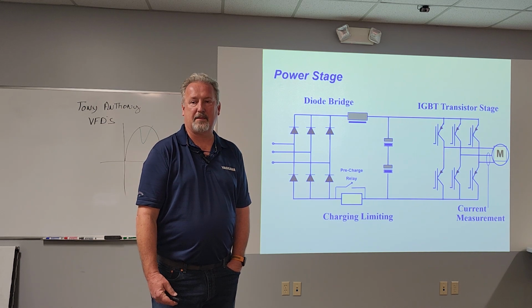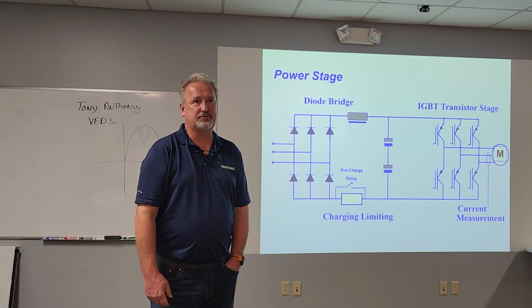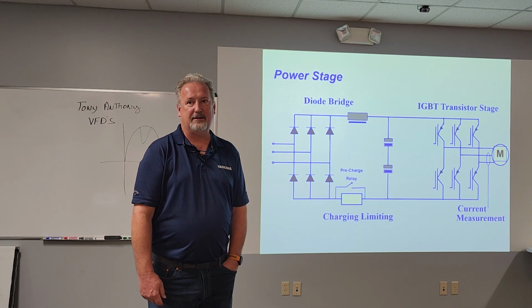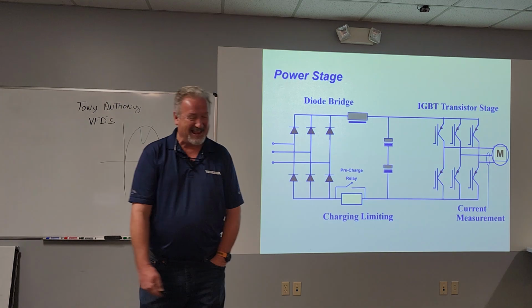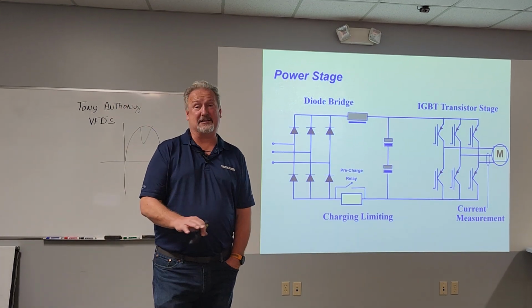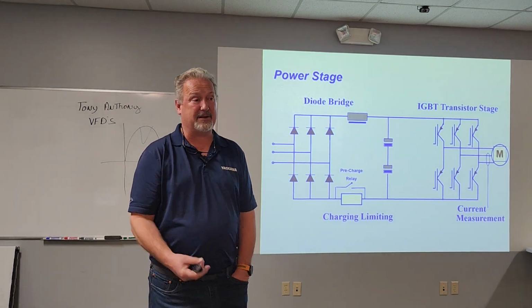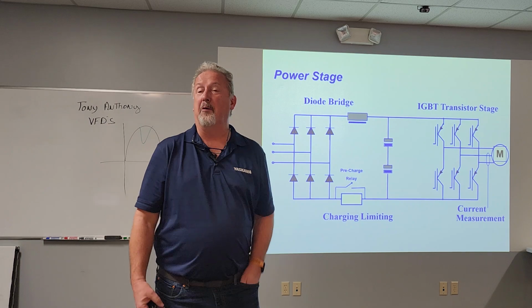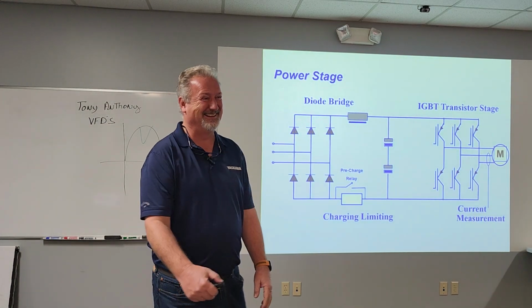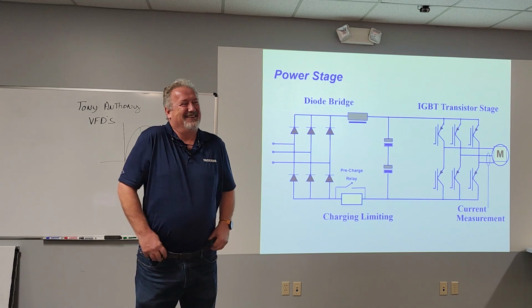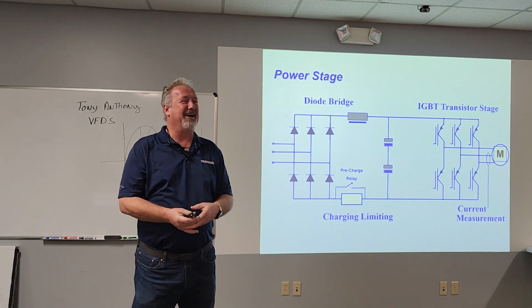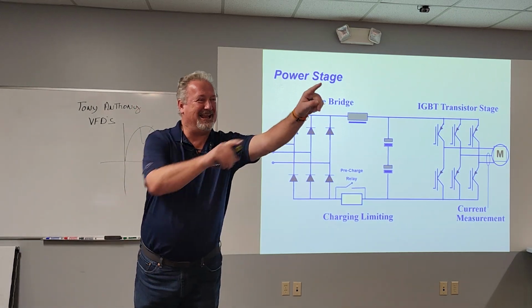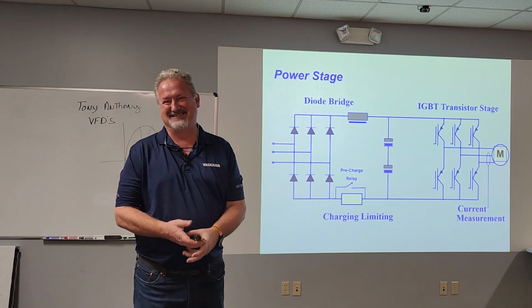What's the general discharge time after you shut a drive down? 3 cigarettes. Yeah. It depends on the size of the drive and everything. Size of capacity. When that voltmeter on the DC bus says 0, or when your assistant says it's a 0, and the guy went like, "We're good."